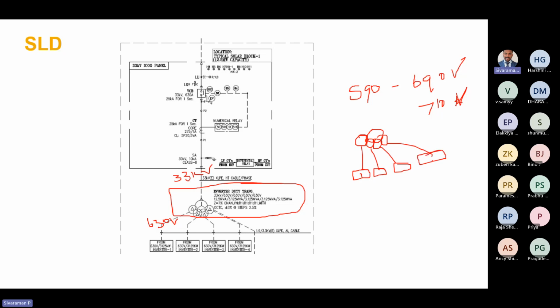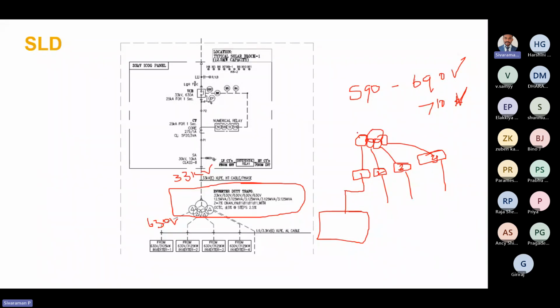So this is inverter 1 and this is inverter 4, this is 2 and this is 3. Okay, so all the DC solar PV panels in series parallel combination, after the stringing etc., will come to the inverter. Similar to that, this will be connected to another set of DC panels. This will be another set of DC panels. Then finally the transformer primary winding will be connected to the medium voltage switchgear in the substation.